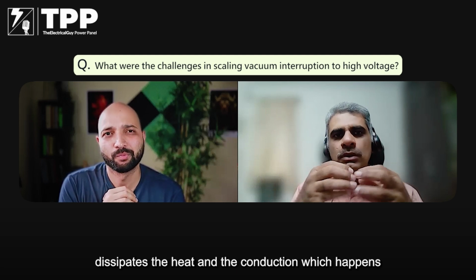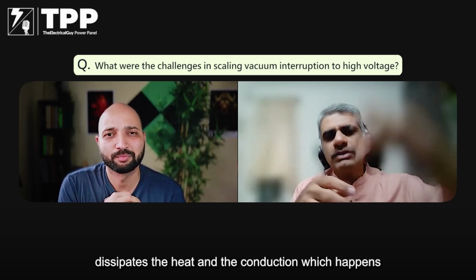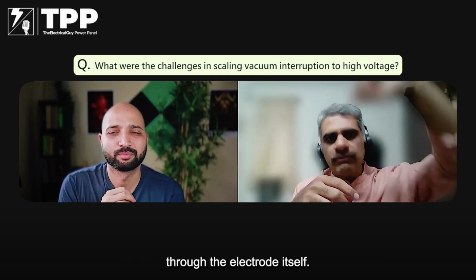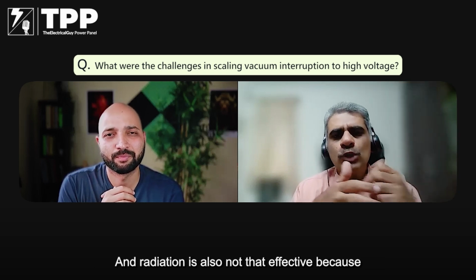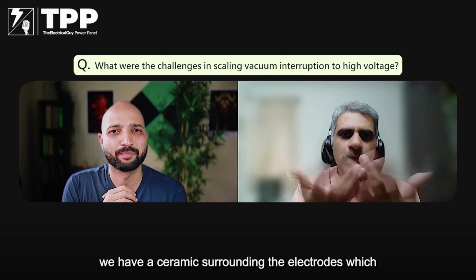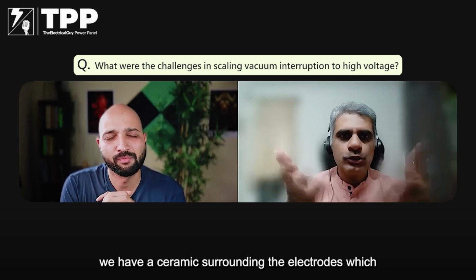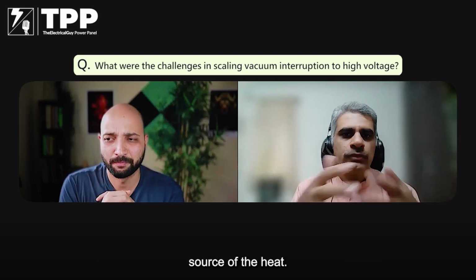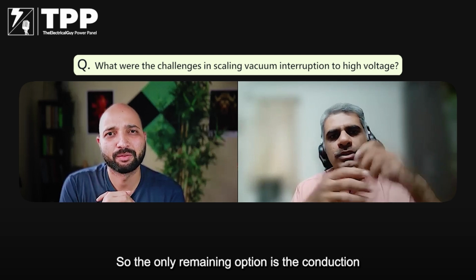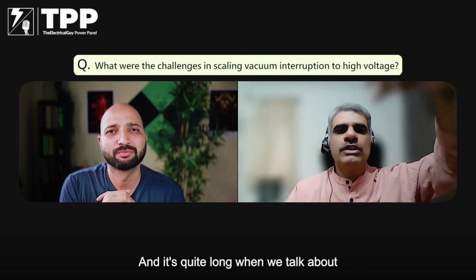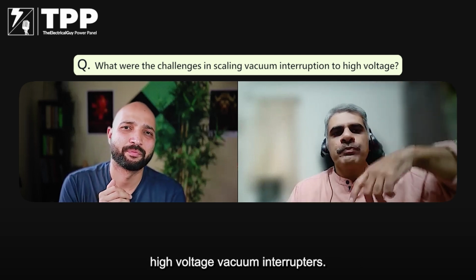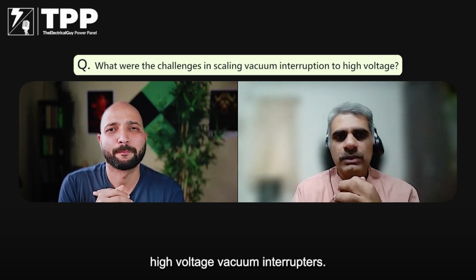which dissipates the heat, and the conduction which happens through the electrode itself. And radiation is also not that effective because we have a ceramic surrounding the electrodes which are carrying the current and which are a source of the heat. So the only remaining option is the conduction of heat through the electrodes, and which are quite long when we talk about high voltage vacuum interrupters.